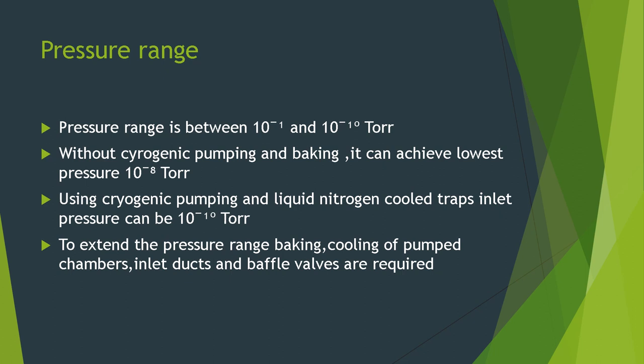Without cryogenic pumping and baking, the pump can achieve a lowest pressure of 10⁻⁸ Torr. Using cryogenic pumping and liquid nitrogen cold traps, the inlet pressure can reach 10⁻¹⁰ Torr. To extend the pressure range, baking and cooling of pumped chambers is used. Inlet ducts and baffle valves are required in the diffusion pump.